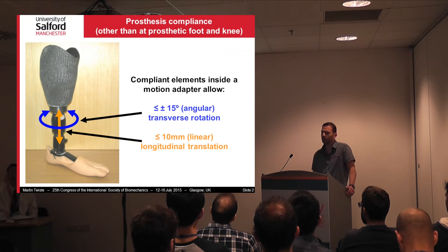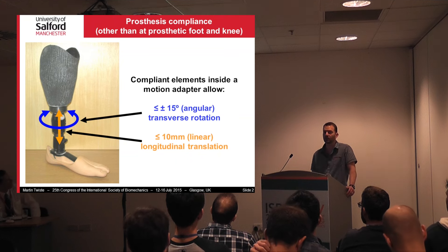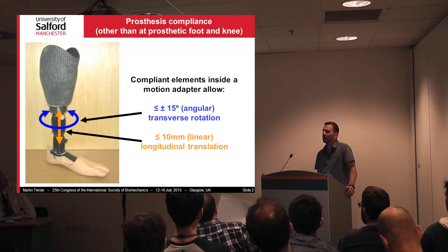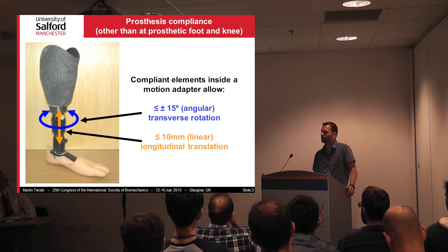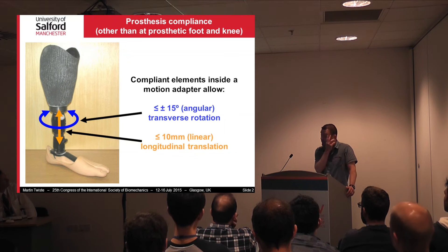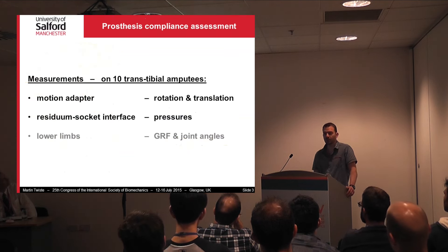Longitudinal translation is a little bit like a pogo stick effect — it allows about 10 millimeters of compression. The reason some amputees have a motion adapter is the transverse rotation aspect, which you can also have to some extent in prosthetic feet but only very little. The transverse rotation is supposed to allow the socket to track motion in the transverse plane of the residual, and the longitudinal translation is there to provide some degree of shock absorption. However, very little work has been done to establish what is going on with motion adapters and their effect on gait.